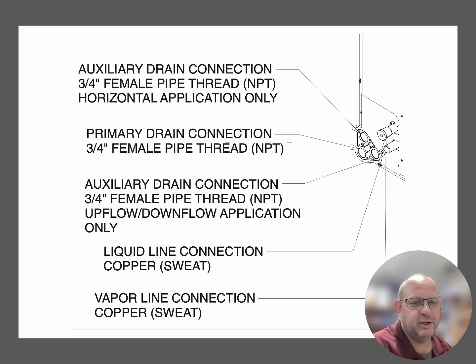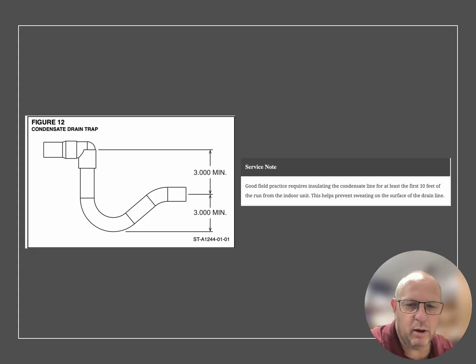The condensate drain is probably one of the more important aspects of these units. We need to drain away that water that we're getting from the air as we're cooling it down. So one of the side effects of cooling air down is that we're going to condense that moisture on the evaporator surface. And we need to take that drain and move that water away from that evaporator coil down a drain somewhere away from the unit.